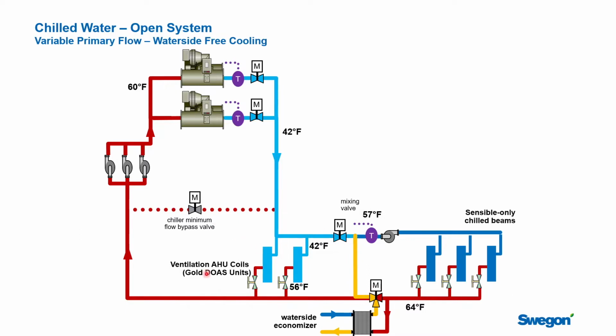Now, as the air temperature drops through the fall and it gets cooler and cooler, we'll reach a point where the outdoor air dew point matches the space dew point. And at that point, we no longer need any kind of mechanical cooling. We're just going to bring outside air into the building. If we have to temper the temperature a little bit, maybe warm it up because it's actually too cold, we would do that with some kind of energy recovery device in the air handling unit, drawing the heat from the return air. And so you're no longer going to have a requirement to produce 42 degree water. You could reset the temperature from 42 to 57 at that point, greatly improve the efficiency of the chiller plant, but you'd still be running the chillers and you'd still be consuming energy to do that.